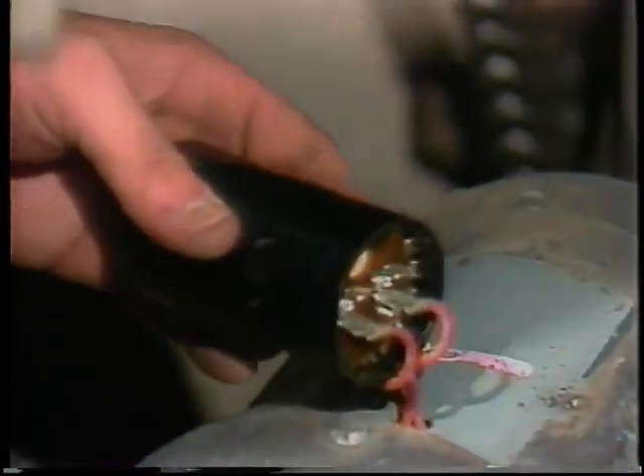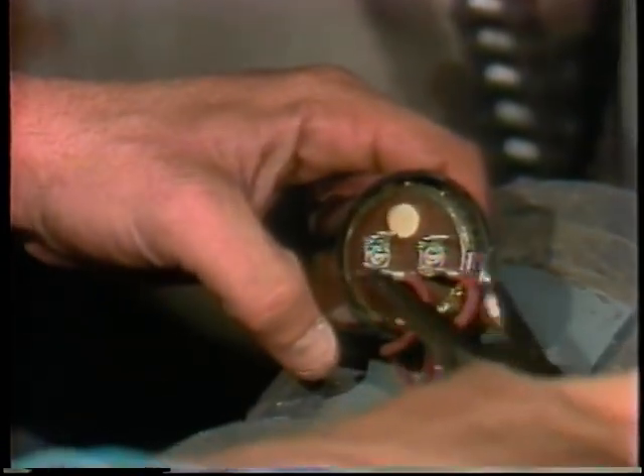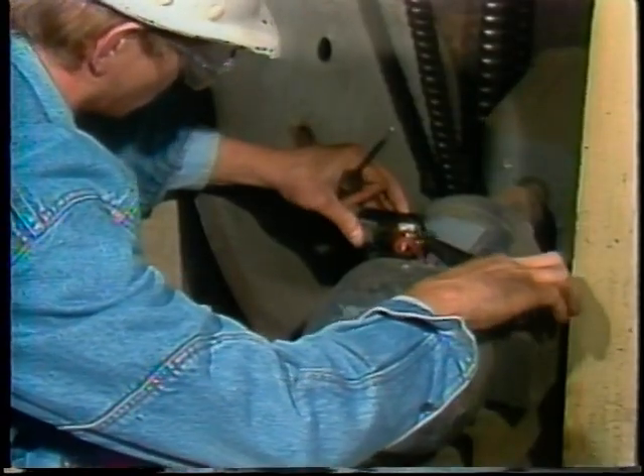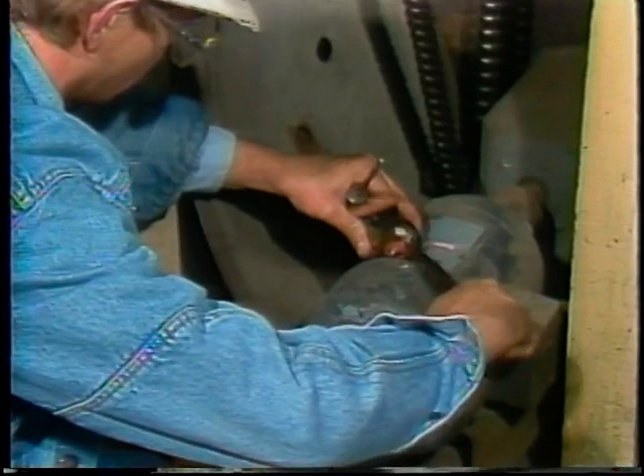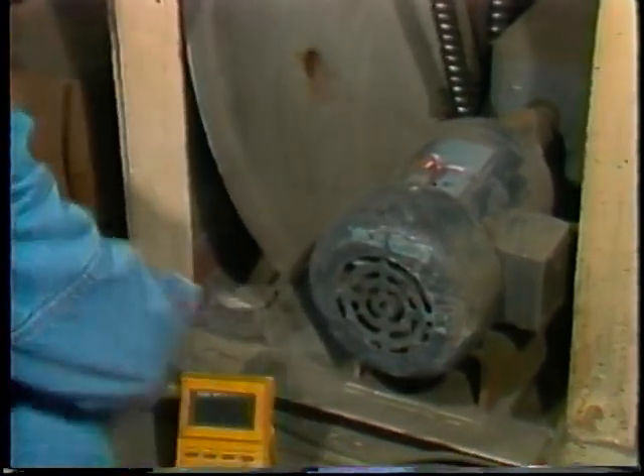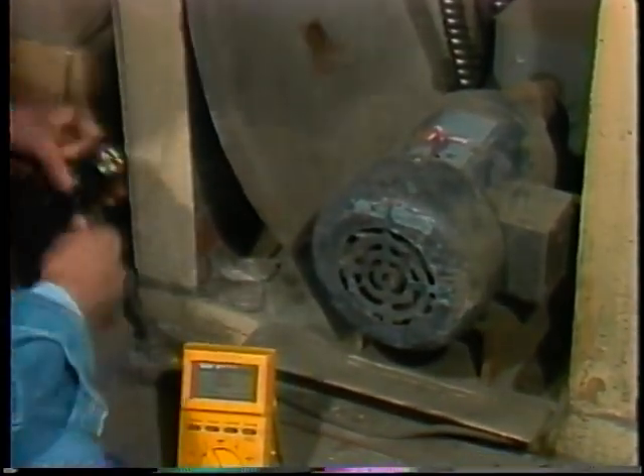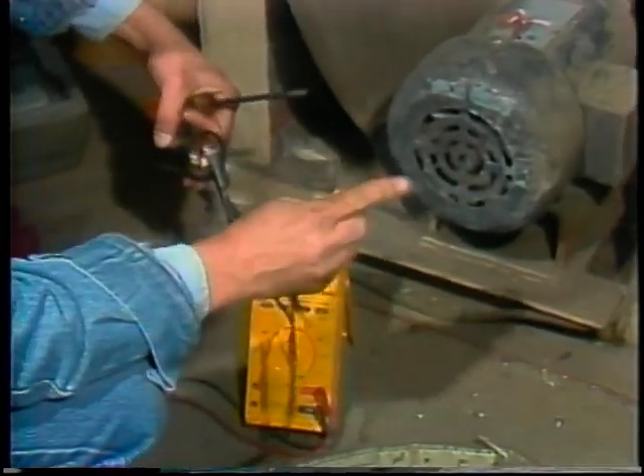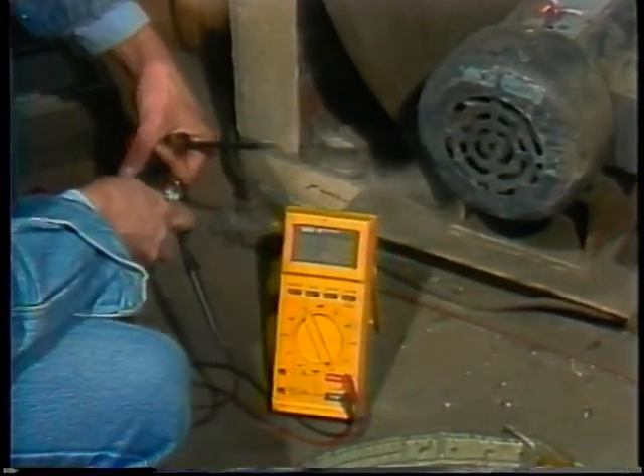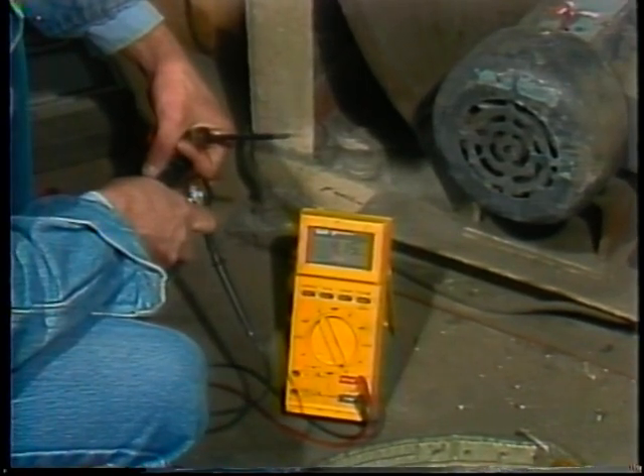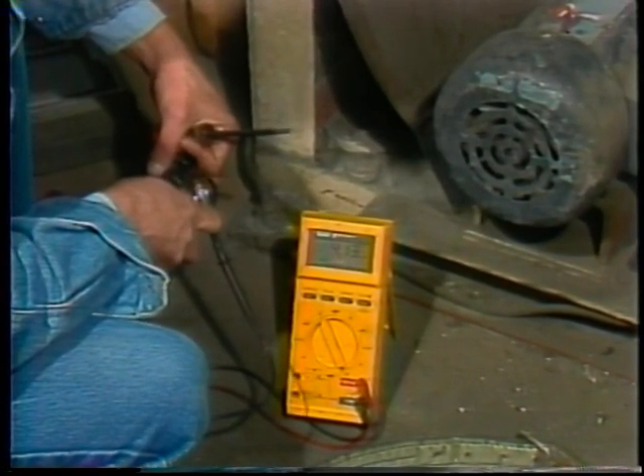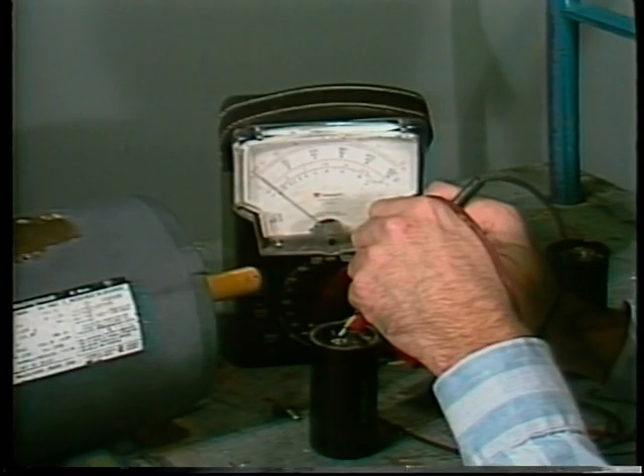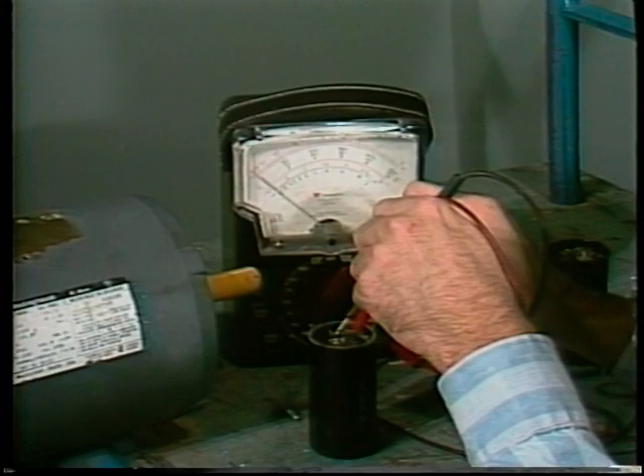The capacitor on capacitor start motors should also be checked periodically. Use the motor's wiring diagram to locate the appropriate terminals. Short the terminals together to be sure the capacitor is discharged. Then, measure the resistance across the terminals. The initial reading may be quite low, but it should build up quickly on a low resistance scale, slowly on a high resistance scale, nearly to infinite as the ohmmeter battery charges up the capacitor. If you find steady low resistance, the capacitor is shorted. An immediately infinite reading means that something in the circuit is open.